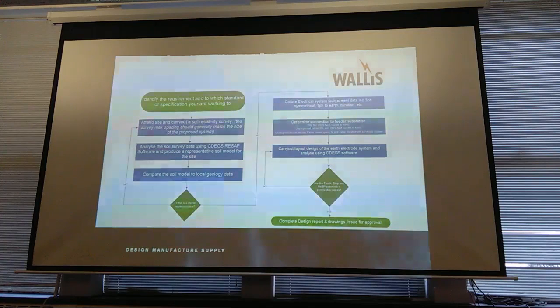So that is just a quick précis of where we go through with a retaining site. Each and every time you are putting an earth electrode system in the ground, you should really be doing a soil resistivity survey. The reason I say that, we might think the geology is the same across the city, same across the general area, but it will change. And it might change significantly, and enough to throw your readings off. So it is good practice to do a soil resistivity survey each and every time. From there, that is your base information. If you get that data wrong, then everything else is going to be wrong as well. So you need to get that right to start with.